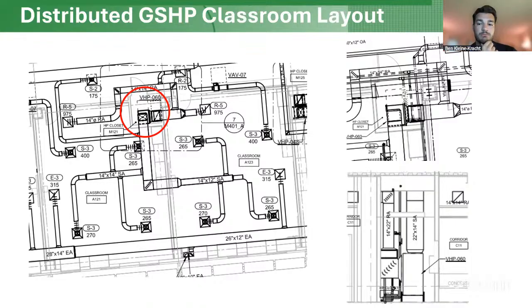If we were to do distributed fan coils with a four pipe system, we could share the classrooms with a fan coil, or one fan coil for two classrooms, but then you don't have as good temperature control, and it's a bigger cabinet that you have to fit above ceiling. So it could be doable, and that would be something we'd talk with you guys about, what you're comfortable with, and whether you'd want those in the space or in the corridor, or how many you're willing to team up. But in general, you want to at least team up the exposures. But none of these options really consider a central air handling unit.